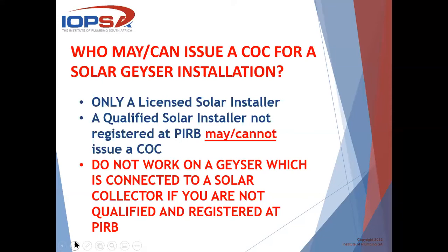It's too big, this, that, and the other. And that just points exactly to what we are saying: if your total system does not comply and is not adaptable to the new geyser, then you will enter into problems. I can tell you that installation cost that plumber close to 25,000 Rand to rectify. So please be careful. Do not step into things and do not work on systems that you don't know and you don't have enough information about.